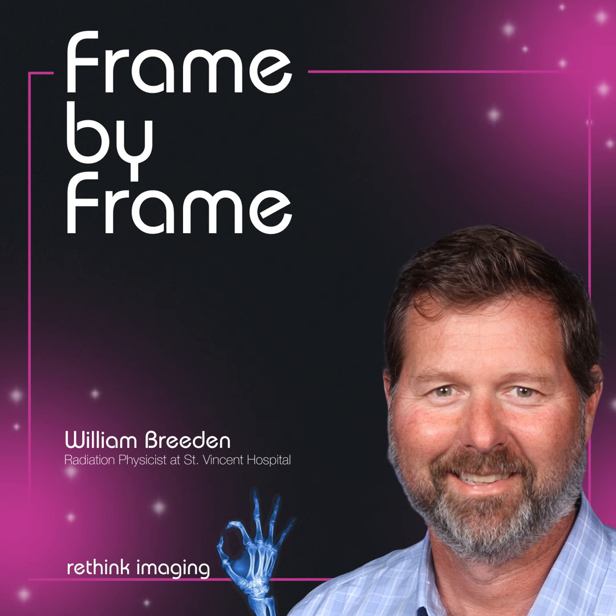And now I'm trying to look 2 days ahead to determine, okay, what do I have scheduled that I'm going to have to basically reschedule, because there are certain modalities that take more precedence over others just due to federal regulations, requirements like that. So, looking at those types of situations, juggling those, obviously normal routine scheduled equipment testing, that's a big part of what we do, going in and testing CT, MRI, nuclear medicine gamma cameras, PET CT scanners, mammography units, ultrasound units. So all of those items have to be tested either through state regulatory requirements or Joint Commission accreditation requirements, or ACR, American College of Radiology requirements, or then there are other accrediting bodies now too, like RADSite, Intersocietal Accreditation Commission, IAC. So there's a lot of moving parts, and you kind of always have something different being thrown at you on a day-to-day basis.